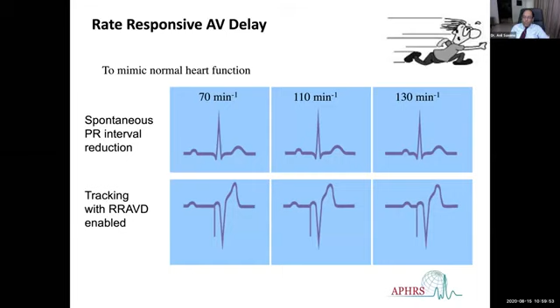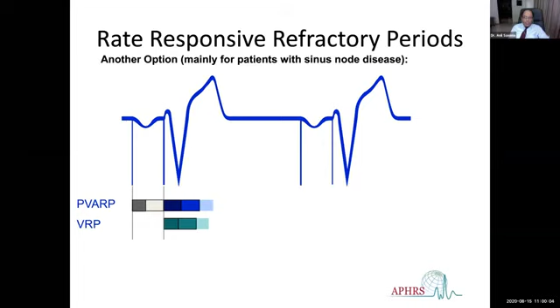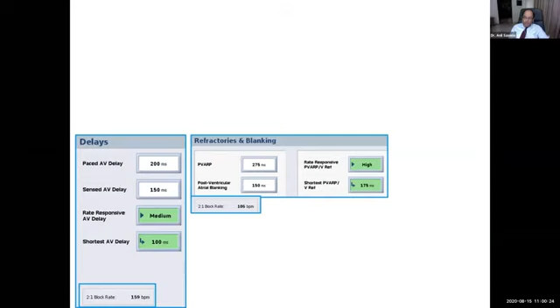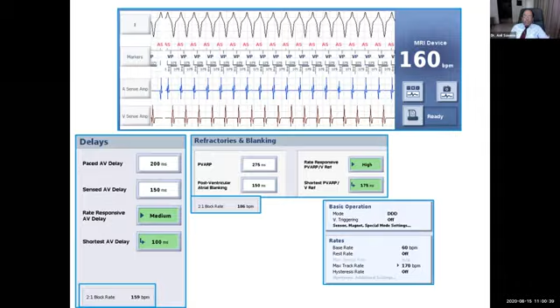And the same thing can be done to the PVARP as well, that at low rate the PVARP is longer, but as the heart rate increases, the PVARP may reduce, and that will allow a higher tracking rate. So that's how we can program. So this patient can be programmed with a shorter AV delay, that is medium, and rate responsive. The minimum AV delay will be about 100. We can program the PVARP also to automatic rate responsive PVARP, and the shortest PVARP can be programmed to 175. That will allow a tracking of 160 heart rate, and we can see when the patient exercises again, the patient has 1-to-1 conduction or response, then the problem is solved.